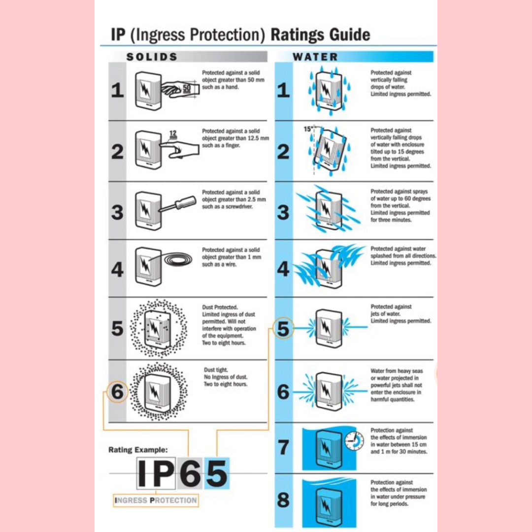Number two talks about protection when falling drops are at 15 degrees tilted, number three covers up to 60 degree inclination, and number four covers splashes coming from all directions. Number five means the object can withstand a jet of water, and number six covers heavy seas or a powerful jet. Number seven is protection against the effect of immersion between 15 centimeters and 1 meter for 30 minutes, whereas number eight covers protection against immersion for long duration.